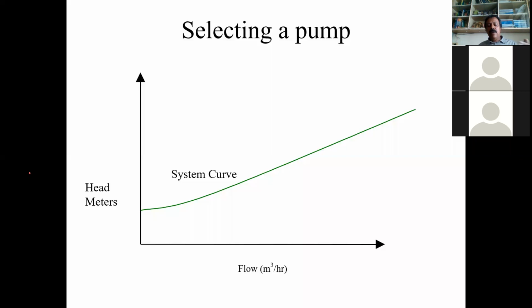hour. So like this, every department keeps adding the factor of safety or margins, and then finally the project engineer who is going to select the pump looks at the design data and maybe 300 meter cube is the actual requirement. But he is also not confident, so he adds his own margin of safety, say 400 meter cube, and goes to the dealer. Dealer doesn't have that 400 meter cube per hour pump. He's got a 500 meter cube big pump, and he's offering to give it at the same price as that of a smaller pump.